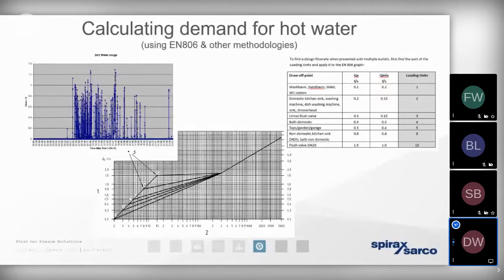So if we're engineering a heat exchanger for a totally new application, could be a new hospital wing, then we can add up the loading units by using sizing formulas such as EN 806. But as we can't accurately estimate peak loads and so forth, it's going to be highly likely that any traditional storage solution is going to end up being oversized.